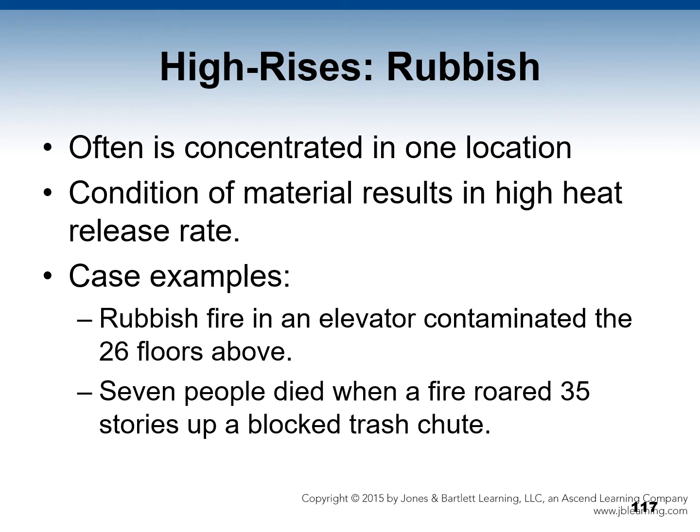One example is a rubbish fire in an elevator that was parked at the 9th floor, and it contaminated the 26 floors above. Trash chutes deliver rubbish to huge compactor units located in the basement. There is an incident where 7 people died when a fire roared up 35 stories of a blocked trash chute.